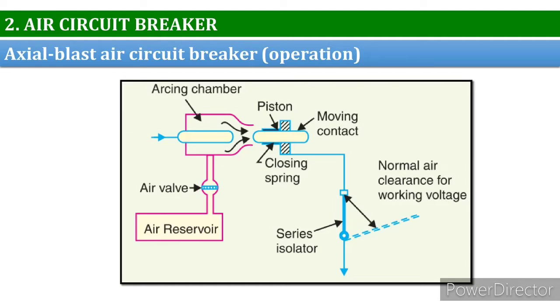Consequently, the arc is extinguished and current flow is interrupted. One important point is that the contact separation required for interruption is generally very small — typically 1.5 to 2 centimeters. An isolating switch is incorporated as part of this type of circuit breaker.